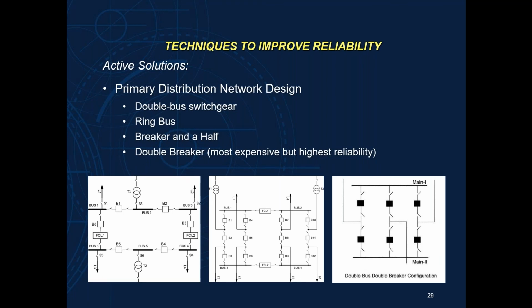You have ring bus design, where you could take any one of these breakers offline and still fully operate, so you can reduce your maintenance time and downtime. The second one, the one in the middle, is a breaker and a half scheme. It's a little more expensive, but you can take more than one breaker offline and still operate without loss. And then finally, on the right, you have a double bus or double breaker configuration, which is full redundancy. These things are very expensive, but they're also going to significantly improve your reliability.